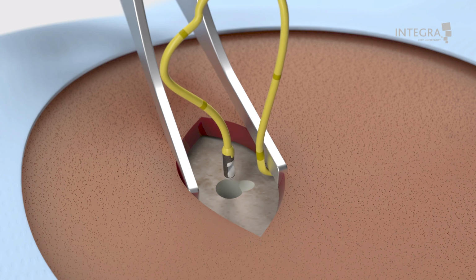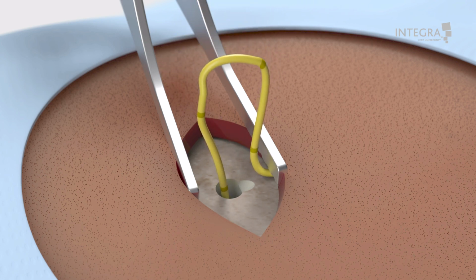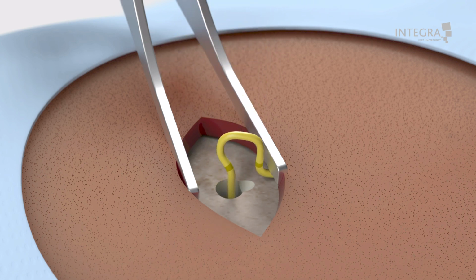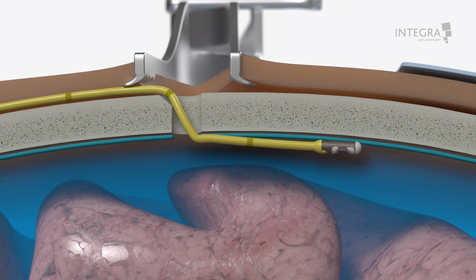For subdural ICP monitoring, place the tip of the ICP sensor on the brain tissue under the dura, opposite the beveled burr hole. The kink must be placed at the bottom of the burr hole, so that the sensing element faces the cortex, as shown in the picture. To ensure accurate subdural ICP monitoring, the sensing element must be facing the cortex. Failure to position the sensing element facing the cortex may result in inaccurate ICP readings. To minimize movement artifacts of the bone flap, place the ICP sensor under the intact skull.